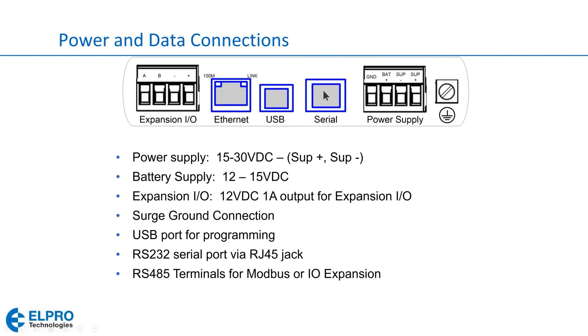We have a serial port — an RJ45 jack — which looks identical to the Ethernet connector. When plugging in an Ethernet cable, make sure you're plugging into the correct RJ45 jack; you can confirm by looking at the two LEDs to make sure they are on. The reason we don't have a DB9 connector is simply there was not enough space on the circuit board. There is also a USB port for programming only, not data communications. My preference is to always use the Ethernet port for programming, since we're always connecting to Modbus devices.